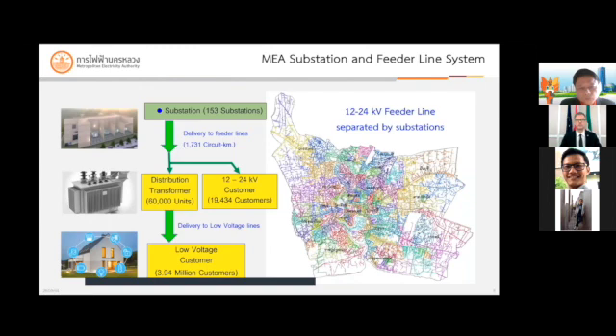This picture shows MEA substation and feeder line system. Substations will step down the voltage to 12 or 24 kV and transmit the power through feeder line system. Feeder line system means network of conductors which feeds power in different localities from substation. These feeder lines will supply 12 and 24 kV customers and distribution transformers, which will step down the voltage and transmit the power to low voltage customer.